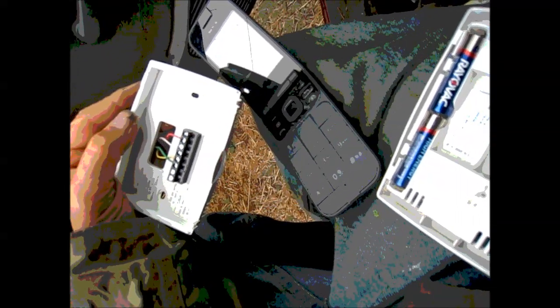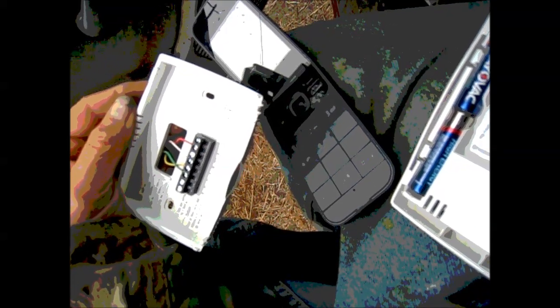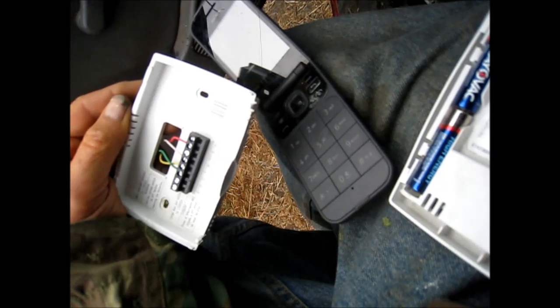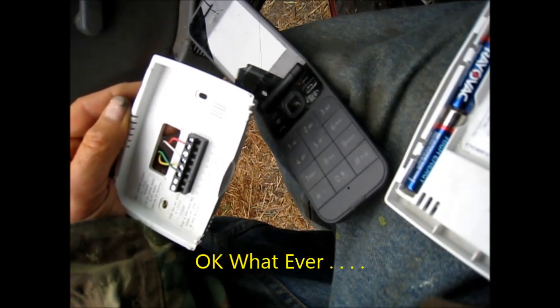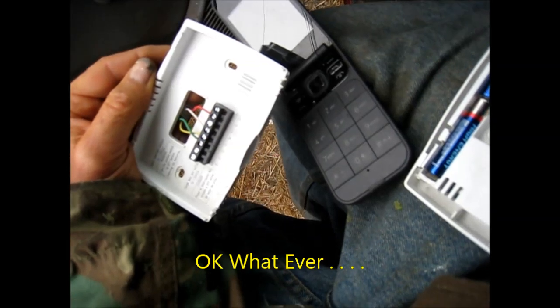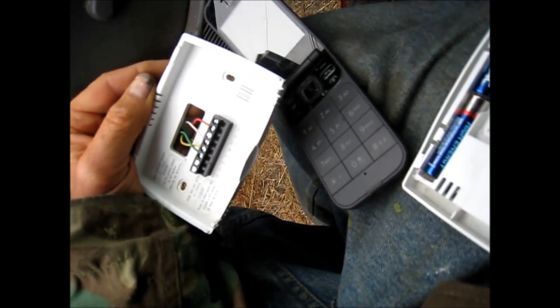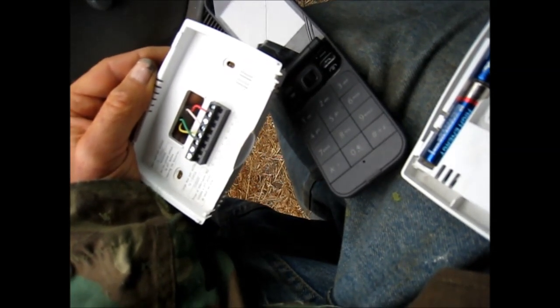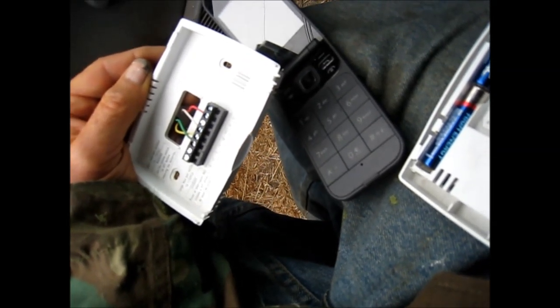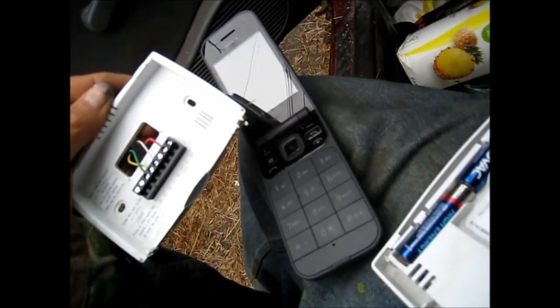Oh, a jumper between R and RC? Yes, I see that. So RC - we need that jumper because we have the internal heater. In case you don't have a wire in particular for RC, then just leave the jumper because we need to power up this terminal too. So I need that jumper on there because I don't have an external heater, is that correct? You need a jumper between R and RC because we don't have a wire giving power to the RC terminal, and the RC terminal leads to the cooling transformer. That's why we will need a jumper there. Oh, the RC is for the cooling transformer. Okay, well thanks for answering the question. Thank you very much for calling.